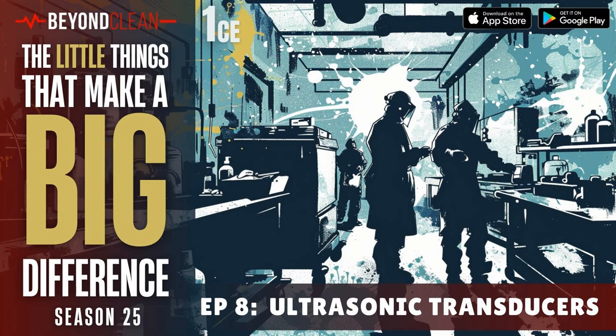And you also have made the transition as we work from definitions into the rest of this interview easy, because we're talking today about little things that make a big difference, right? And as we think about the big difference that ultrasonic cleaners make, you mentioned some instruments that maybe have certain cracks and crevices that are difficult to clean. Just in your experience working with ultrasonic cleaners and working through the process of getting FDA clearance for cleaning certain types of instruments, could you maybe paint a thumbnail for us of how important you think ultrasonic cleaning is for patient safety and for instrument cleanliness?